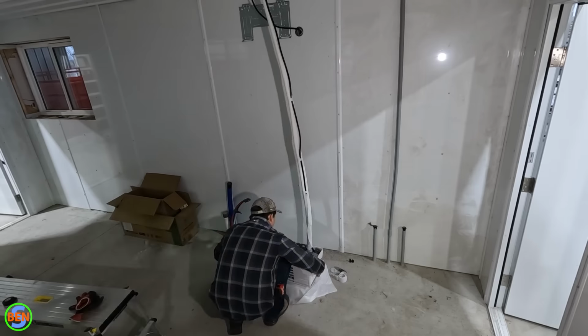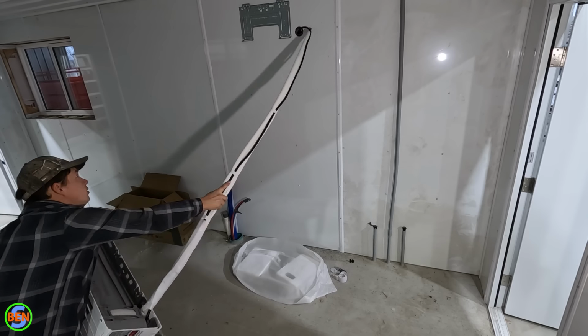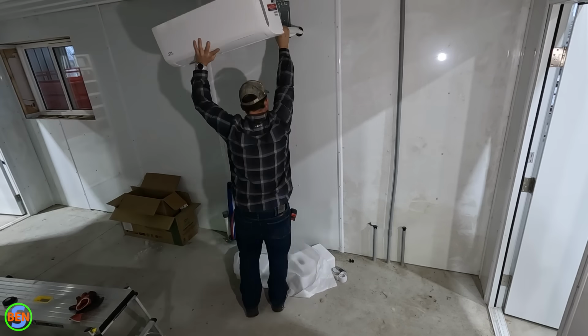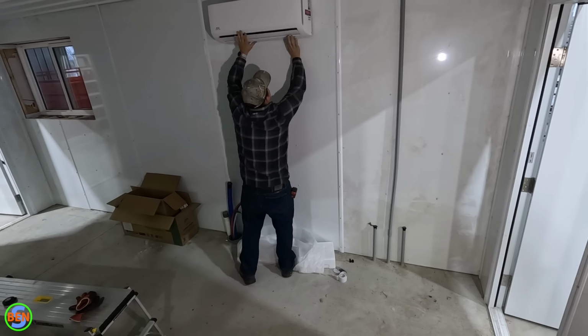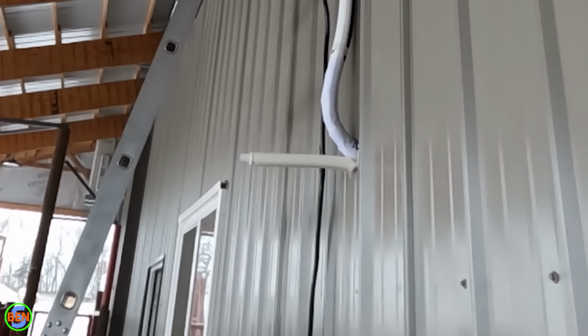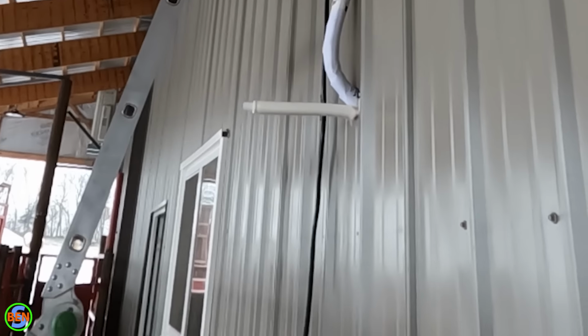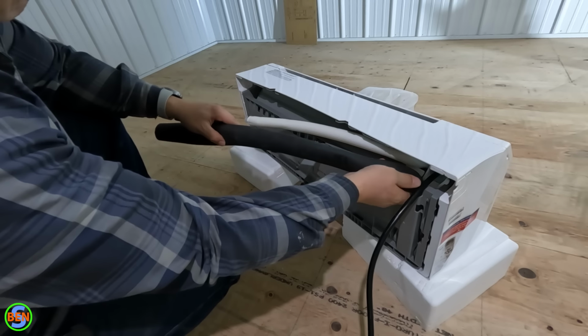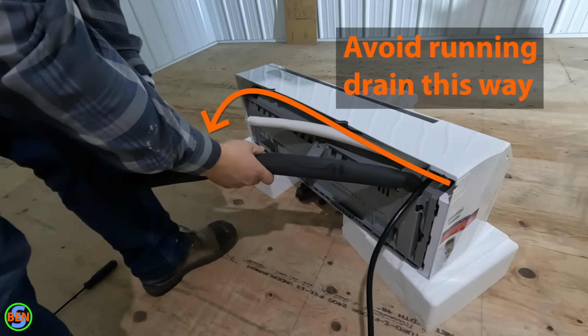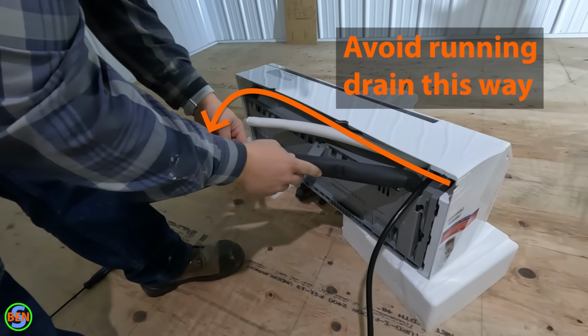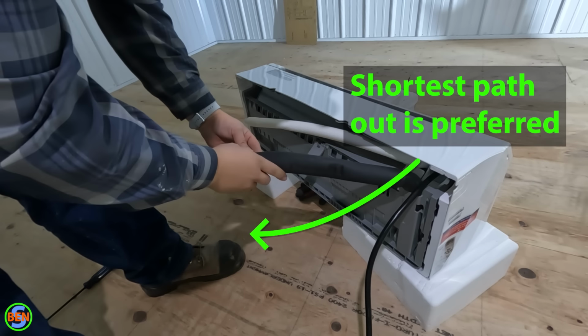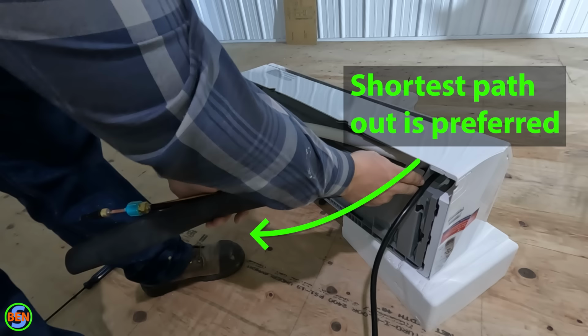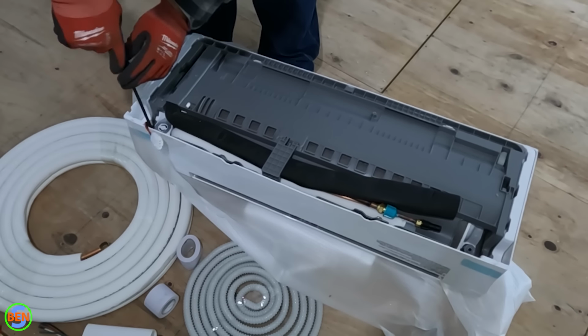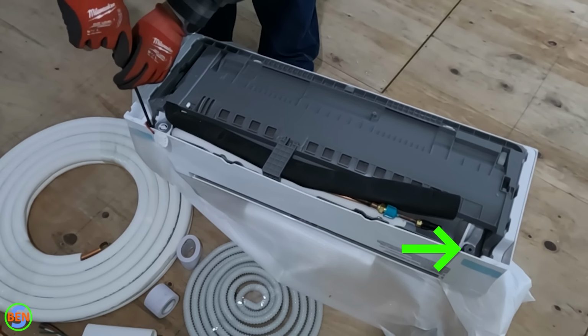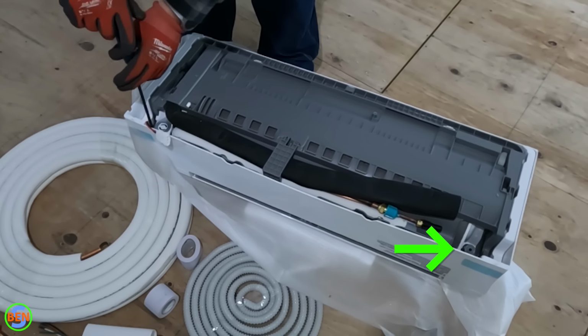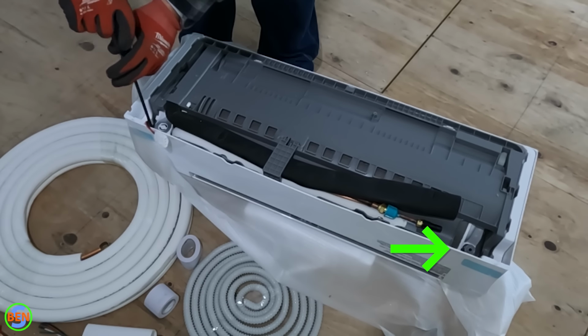Now, with the wall hung units, I would highly recommend, if at all possible, make that condensate drain run directly out of the unit, like straight out the back and outside, or as close as possible. I really don't like having to run the condensate drain to the opposite side of the unit and then out. Sometimes you can actually switch which side the condensate drains out. You can pull a plug and switch it over so it drains out of the left or the right. So definitely check that to make sure.